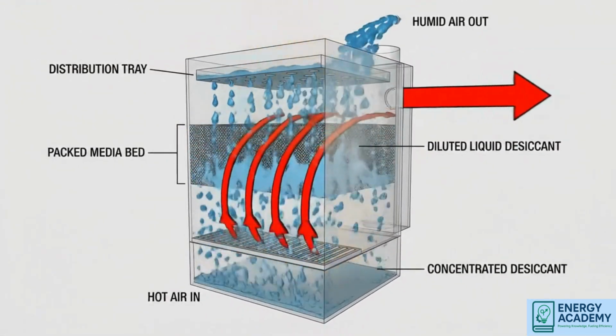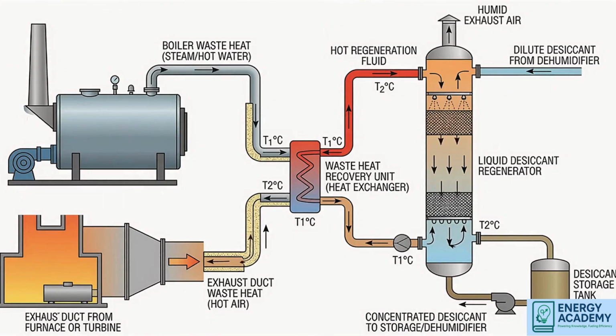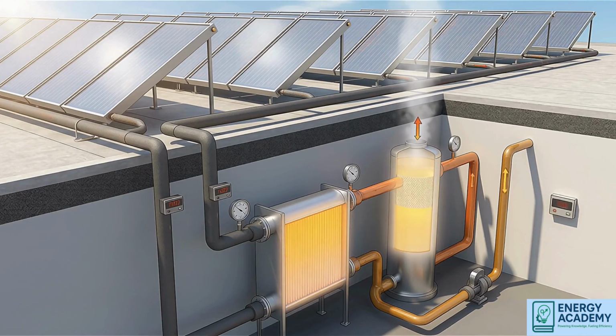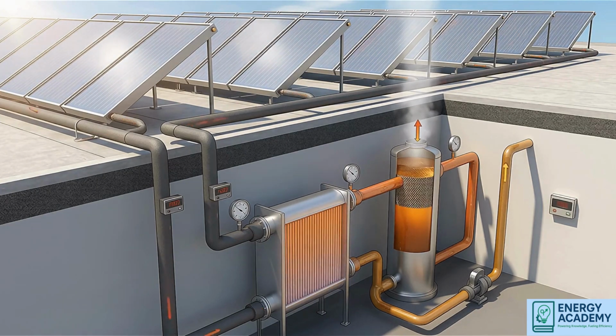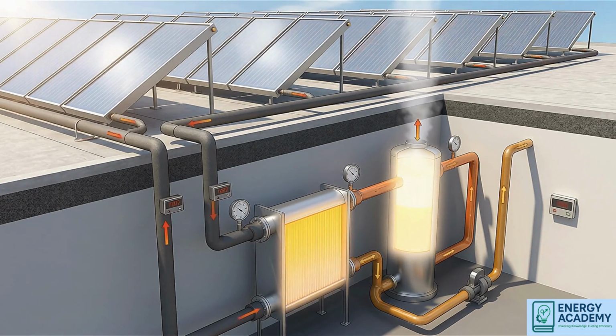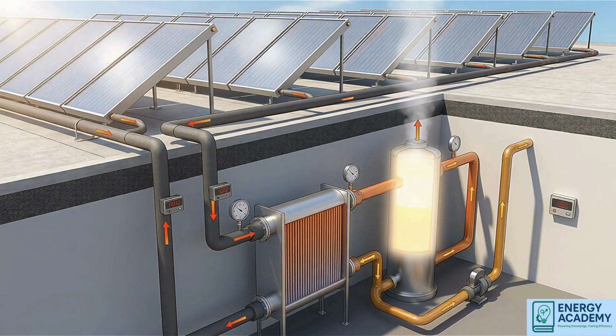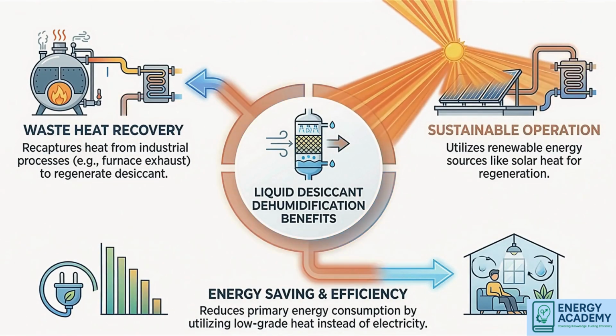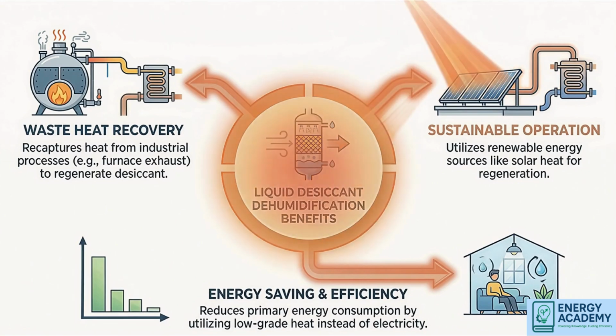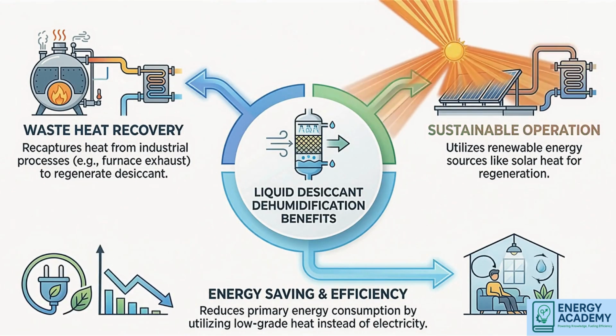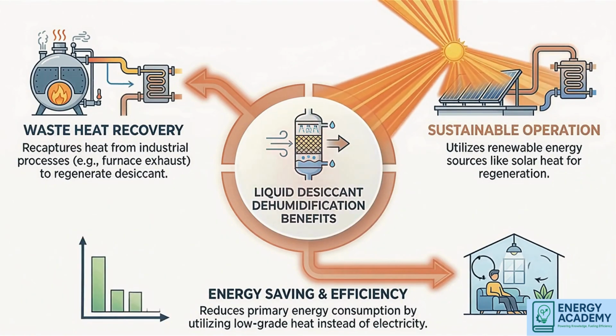In factories, waste heat from boilers and processes can be directly reused, turning waste energy into cooling. Even solar thermal energy can regenerate the liquid desiccant, allowing DEVAP to operate with minimal electrical input. Ultimately, liquid desiccant-based DEVAP separates latent and sensible cooling, reduces energy use, and enables sustainable cooling.